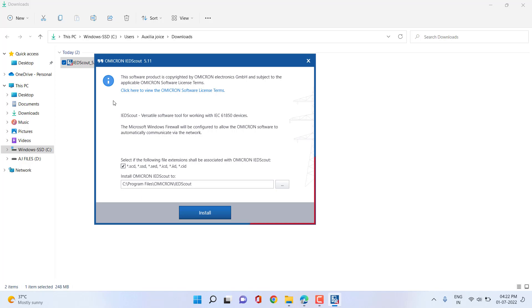NPcap is important to capture client-server and GOOSE messages in the network. During installation, by default the checkbox for different types of SCL files is enabled. The first three SCL file types are system specification files: the Substation Configuration Description, System Specification Description, and System Exchange Description. The other three files are IED-specific: the IED Capability Description, Instantiated IED Description, and Configured IED Description.